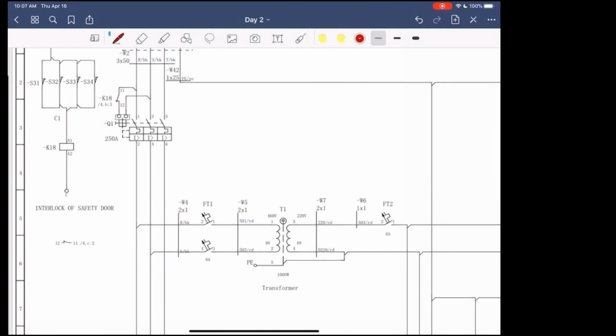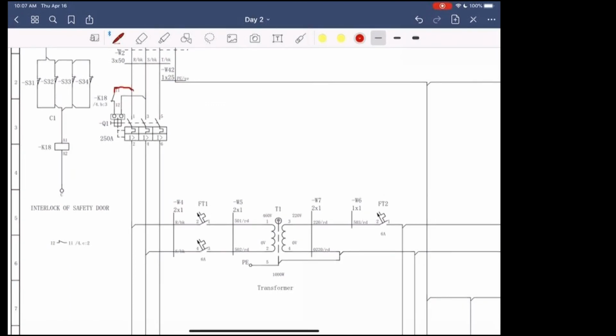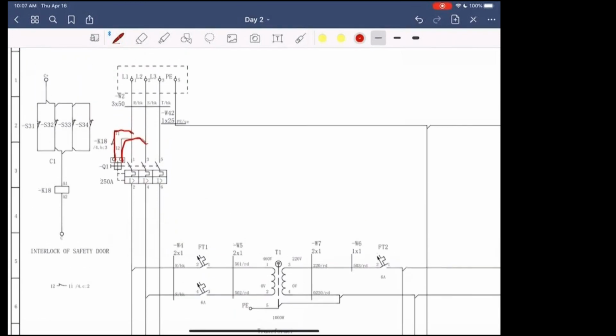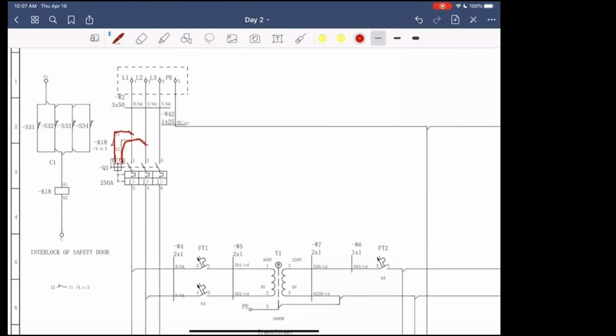So again, you have a shunt breaker. If you notice, the shunt breaker is on the live end of the power. It is always live. Inside the cabinet, there is a terminal switch with a terminal plate that has these connectors. You have to know that when you open the cabinet, even if you shut the power off on the machine, these two lines are going to be live all the time. Unless you disconnect the power at the source, those will always be live.